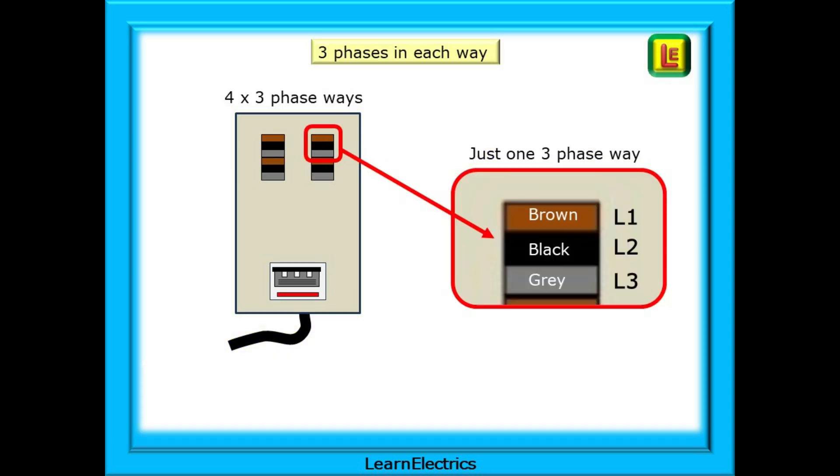Each way will have an L1, L2 and L3 terminal. We will use the harmonised colours of brown, black and grey. Older boards will have red, yellow and blue for the phases with black as the neutral. Some will have all black or even all white. In fact, if you're about to work on an existing board, assume nothing. Carry out your own checks and establish just what colours have been used.